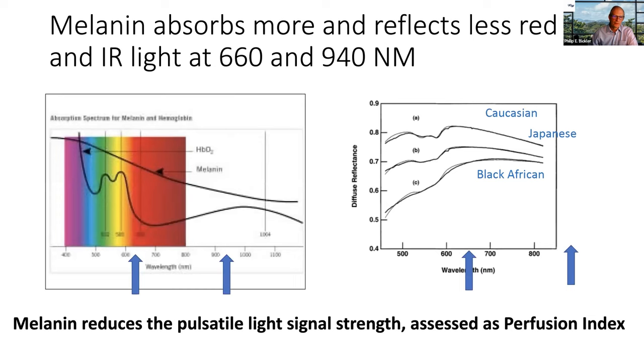The problem with pulse oximetry can be seen here. In the lower left, there's a chart of the light absorption of melanin, and you can see that in the red light spectrum, the absorption of melanin varies with wavelength. Pulse oximeters, because they use light-emitting diodes, don't produce a pure wavelength of light - they actually produce a bell curve-shaped distribution of light. Because melanin absorbs more red light at the shorter wavelengths, it produces a skew or a bias in the red light signal. That's the basis for this issue.